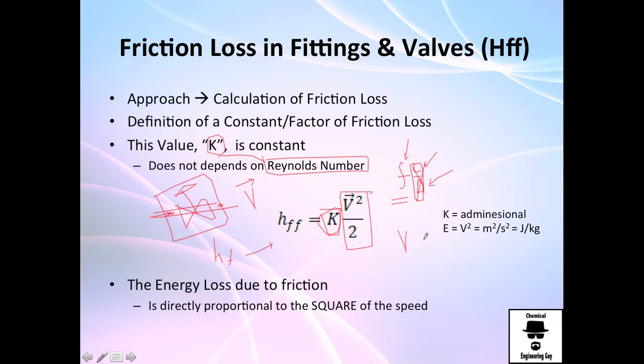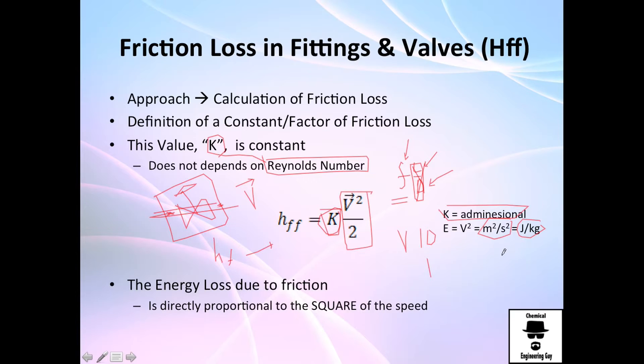Even if you have a high speed of maybe 10 m/s or a low speed of 1 m/s, you will still use the same value of K. K is dimensionless, so velocity squared (m²/s²) divided by 2 gives units of joules per kilogram. Also note that friction loss is proportional to velocity squared — more speed means more friction loss.